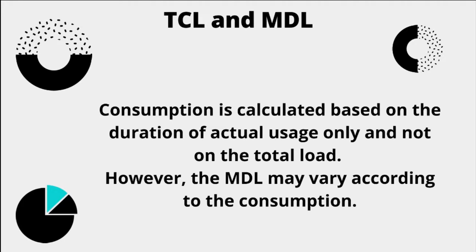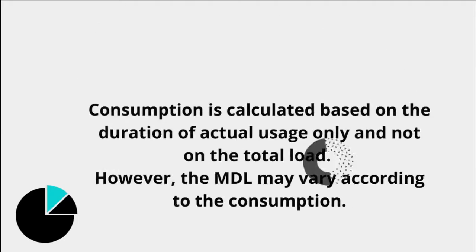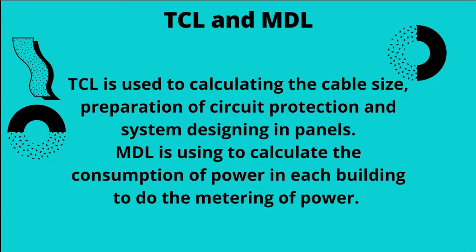However, the MDL may vary according to consumption. TCL is used for calculating the cable size, preparation of circuit protection, and system designing in panels. MDL is used to calculate the consumption of power in each building for the metering of power.